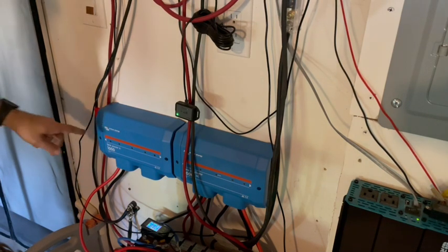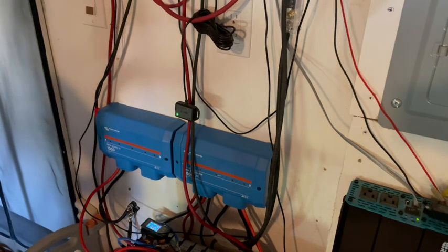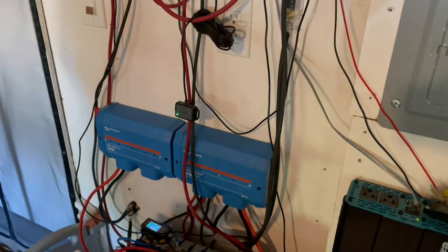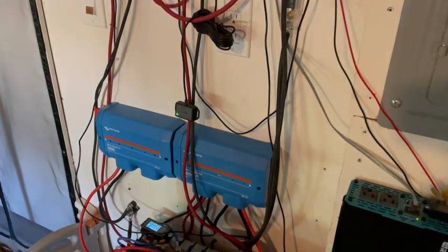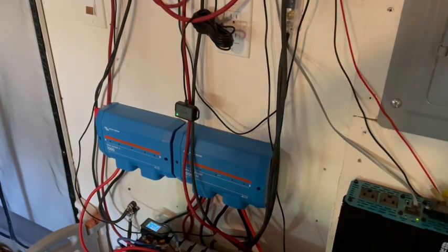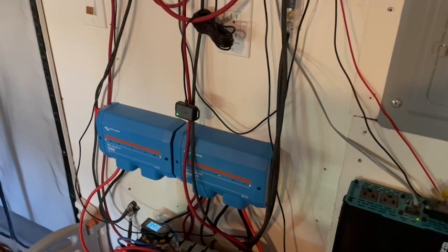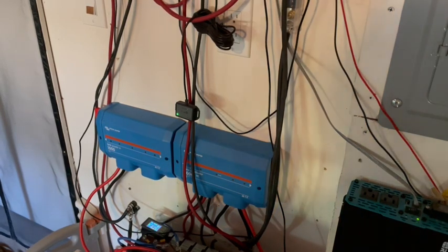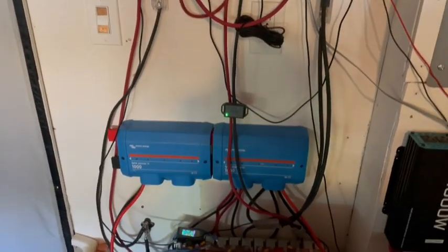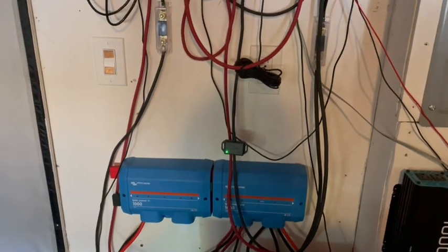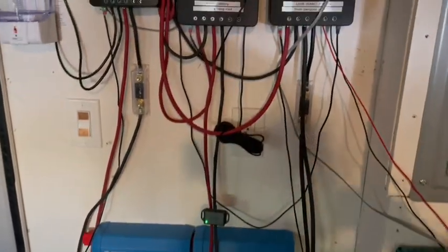The only thing that's off is that the fuses are 250 amp fuses, and I suspect that the transient current bursts might be higher than that in some places. Like when a refrigerator starts up, I've seen 110 amps come out of a refrigerator, even though it draws only 10 amps when it's running.